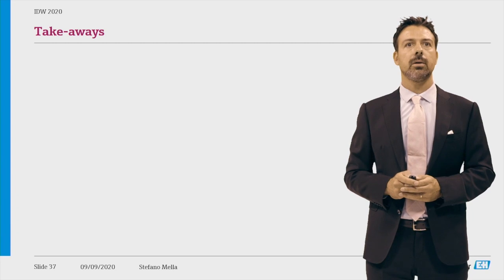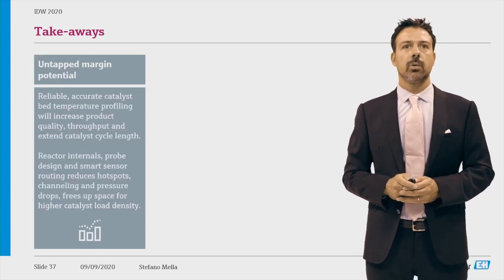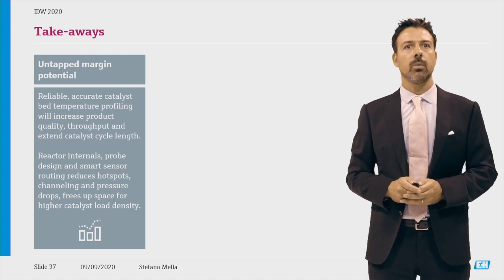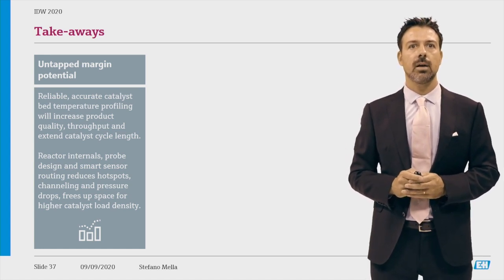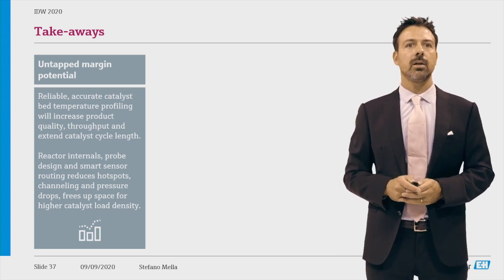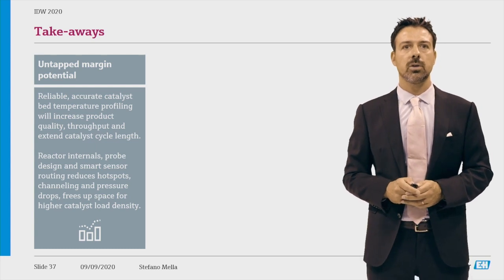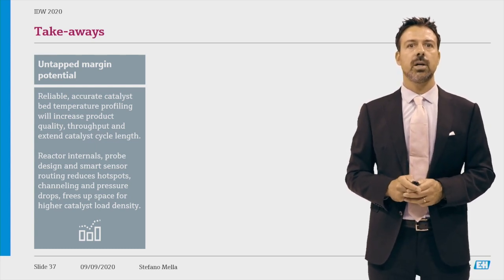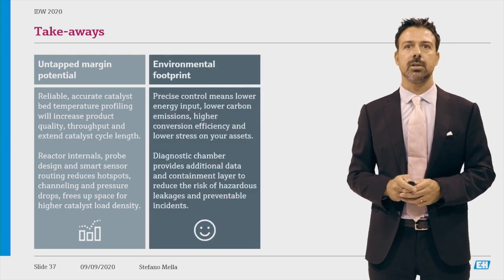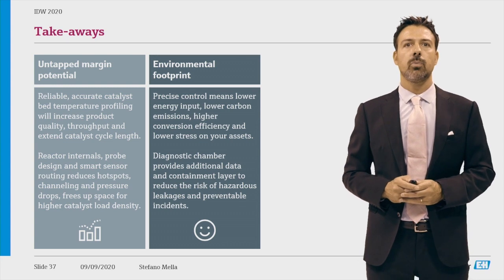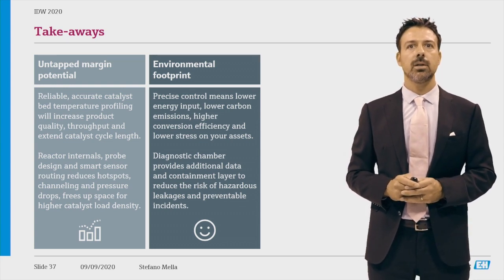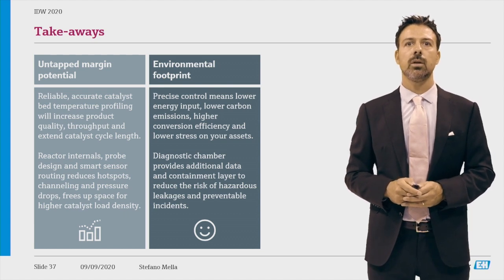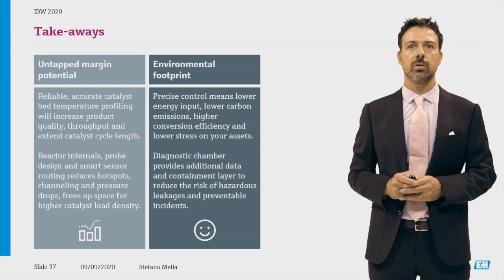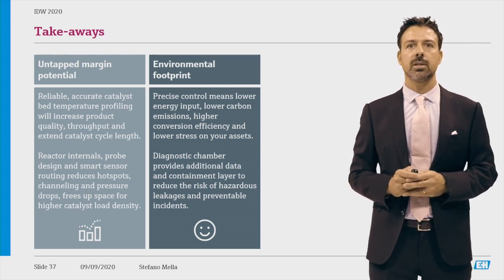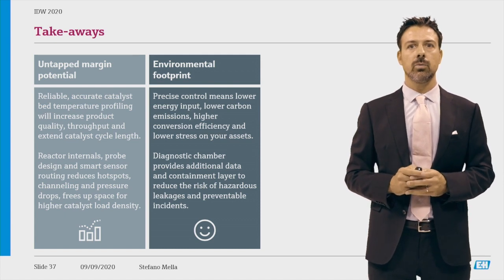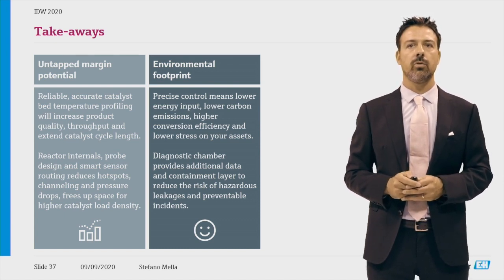And now let's go to the last part of my presentation. I want to start talking about untapped margin potential. So reliable, accurate catalyst bed temperature profiling will increase product quality, throughput, and extend catalyst cycle length. Reactor internals, probe design, and smart sensors routing reduces hotspot, channeling, and pressure drops, frees up space for higher catalyst load density. When we talk about environmental footprint, we know that precise control means lower energy input, lower carbon emission, higher conversion efficiency, and lower stress on your assets. So the diagnostic chamber provides additional data and containment layer to reduce the risk of hazardous leakage and preventable incidents.